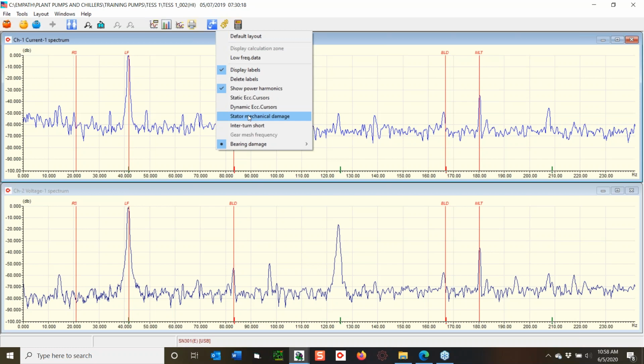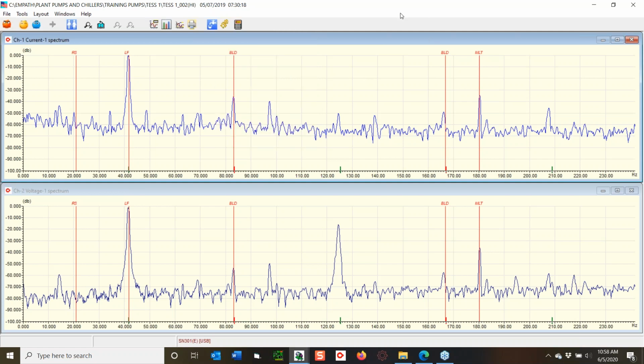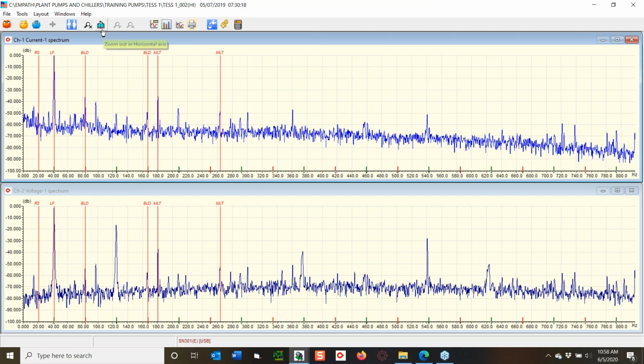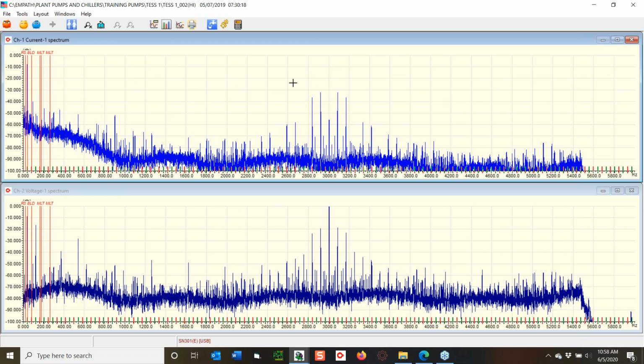So the stator, it says stator mechanical damage. What that is basically is the running speed times the stator slots, plus and minus the line frequency. When I see that in a VFD application, it can also be related to little discharges going on between turns. It's a random-wound machine, so not too surprising. And when I have those types, and here's, by the way, where I step back, there's a single hump here versus others, and you'll see all those will line up with these peaks down here, which I call the Christmas tree.